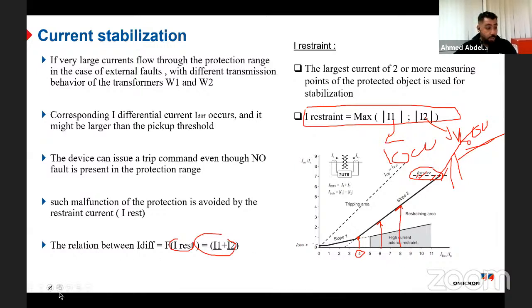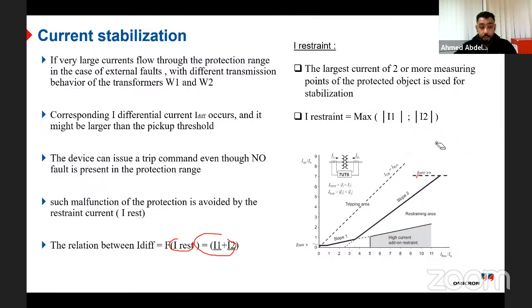Another thing which is important to know here, which is very important, by the way, especially in Siemens relays, for the people who will deal with a Siemens relay, we call it high current add-on stabilization. This is a very technical thing in Siemens relays to avoid the relay tripping in case the restraint current is increasing slowly, to avoid CT saturation. What does it mean?